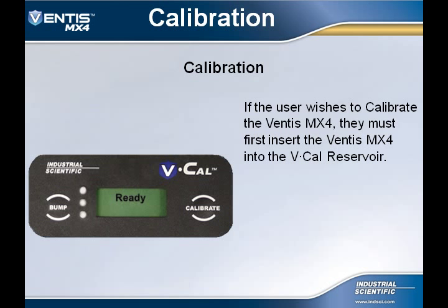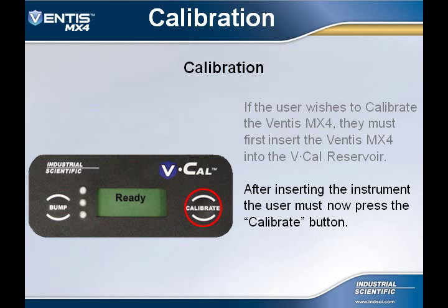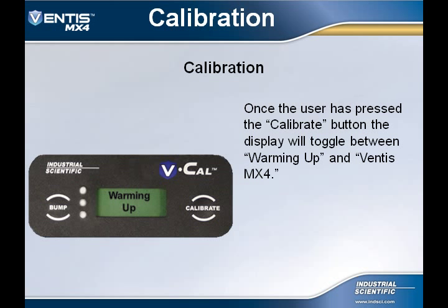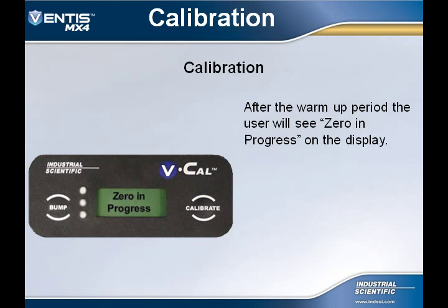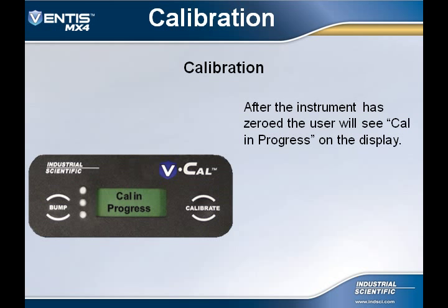To perform a calibration of Ventis MX4, insert the Ventis MX4 into the VCal reservoir. After inserting the Ventis MX4, press and hold the Calibrate button for 3 seconds. The VCal display will toggle between warming up and Ventis MX4. After the warm-up period, the VCal's display will show zero in progress. After the instrument has zeroed, the display will show cal in progress.